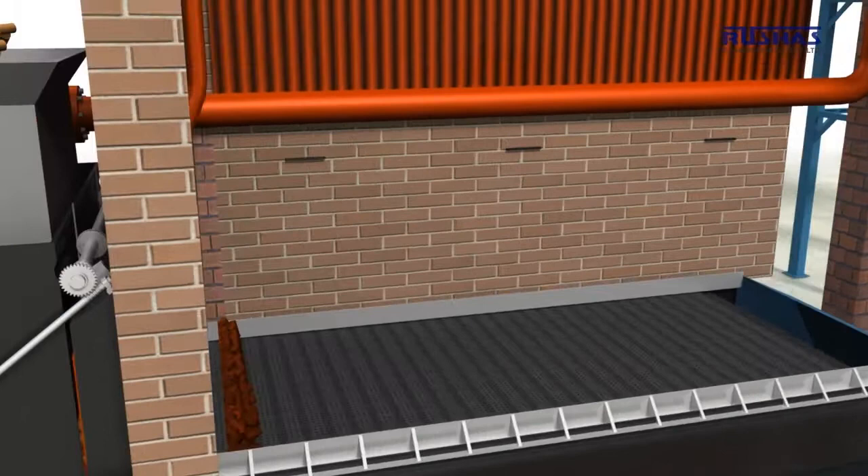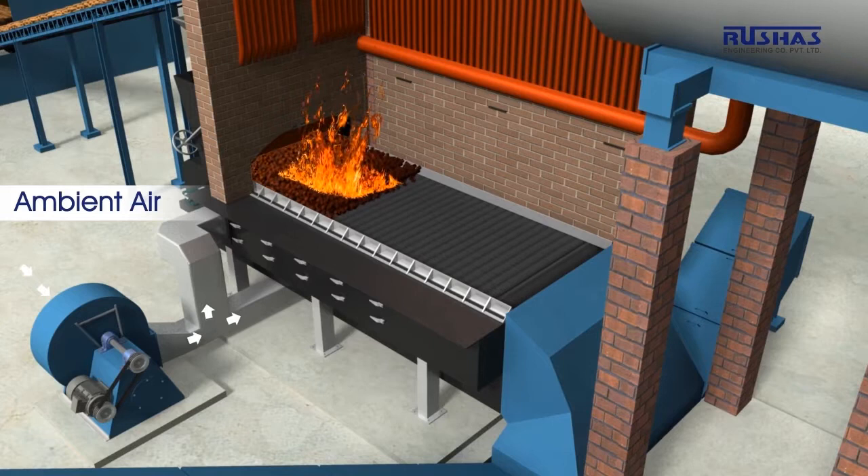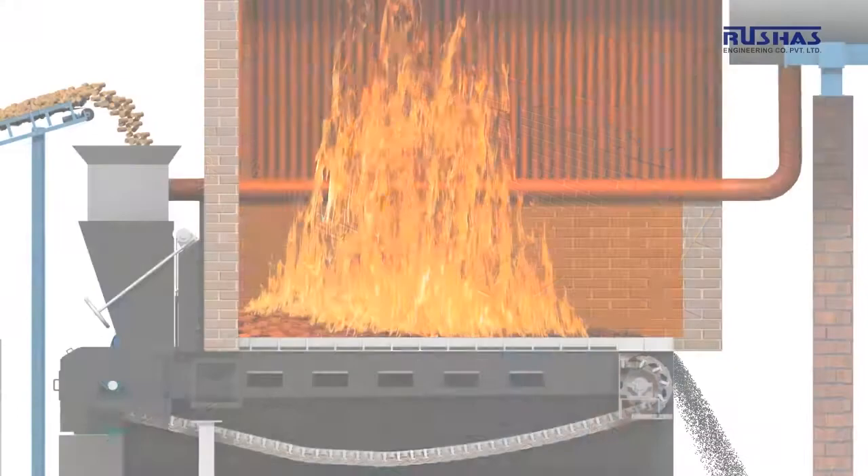An arch made from refractory material is provided at the beginning of the grate area, which initiates preheating of the fuel. Grate bar castings are made from a suitable alloy which can withstand the high temperatures generated at the time of combustion. A FD fan circulates air through the wind chambers provided below the grates.